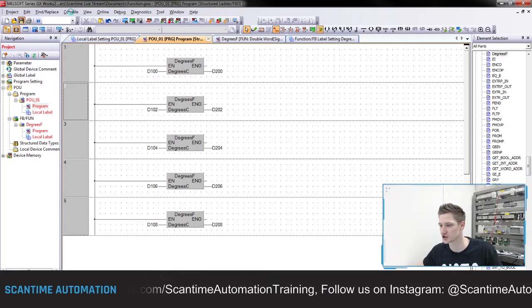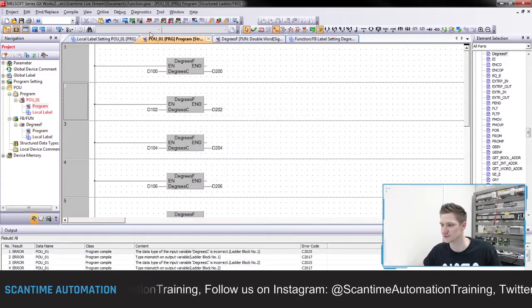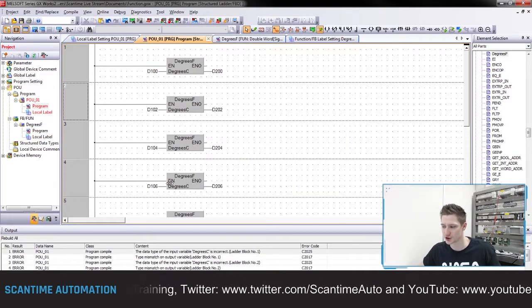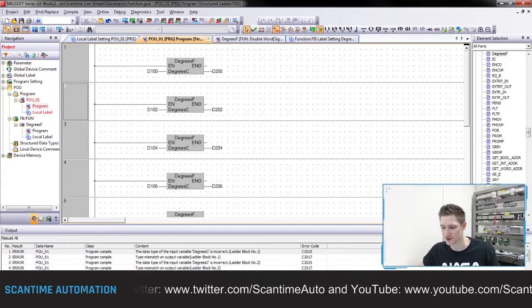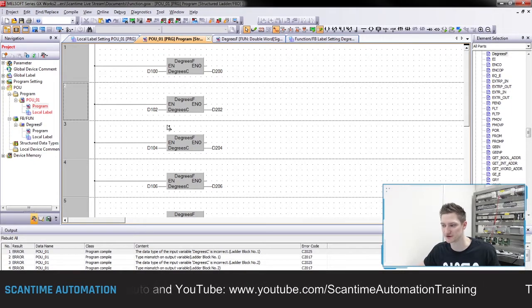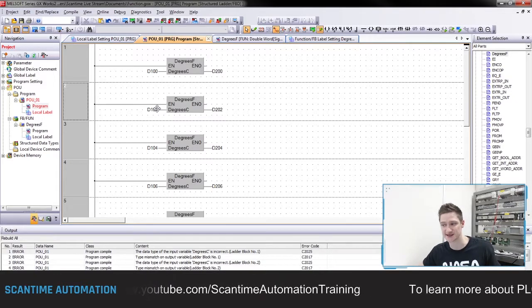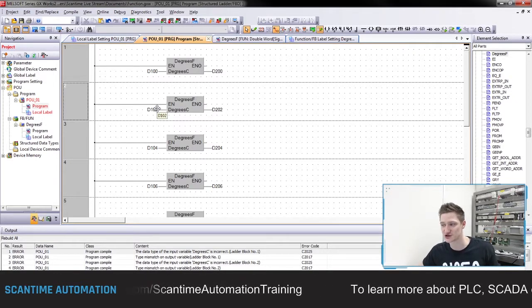Let's save our work, compile, and then let's download that to the PLC. Now you'll notice when I've done a compile here, it's come back with a couple of errors, well 10 in fact, and these 10 errors are actually referring to these D100s and D200 values.